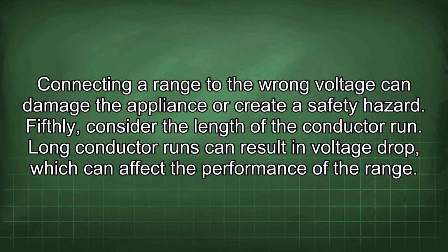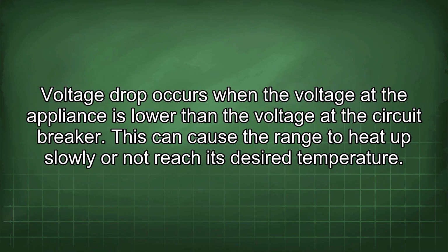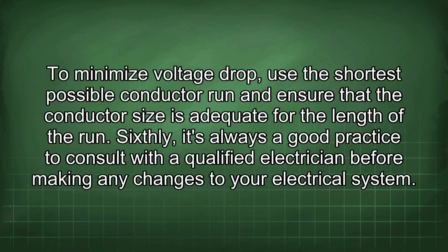Fifthly, consider the length of the conductor run. Long conductor runs can result in voltage drop, which can affect the performance of the range. Voltage drop occurs when the voltage at the appliance is lower than the voltage at the circuit breaker. This can cause the range to heat up slowly or not reach its desired temperature.